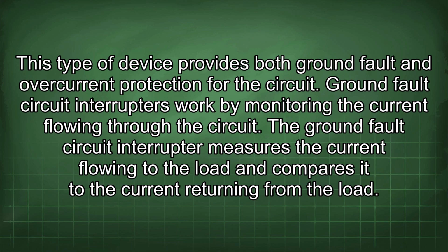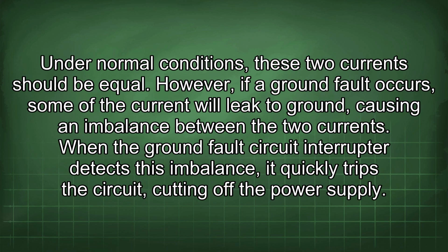Ground fault circuit interrupters work by monitoring the current flowing through the circuit. The ground fault circuit interrupter measures the current flowing to the load and compares it to the current returning from the load. Under normal conditions, these two currents should be equal. However, if a ground fault occurs, some of the current will leak to ground, causing an imbalance between the two currents. When the ground fault circuit interrupter detects this imbalance, it quickly trips the circuit, cutting off the power supply.